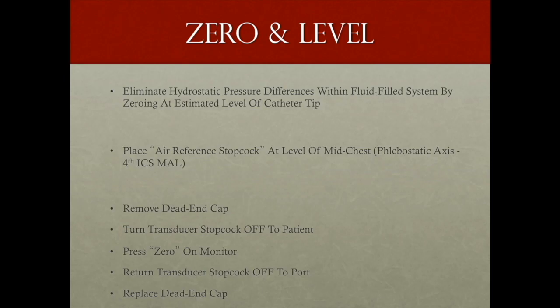The purpose of zeroing and leveling is to eliminate hydrostatic pressure differences within fluid-filled systems by zeroing at an estimated level of the catheter tip within the patient's body. Generally, during zeroing procedures, the stopcock is placed at the level of the phlebostatic axis, which is the fourth intercostal space, mid-axillary line, or the mid-chest.